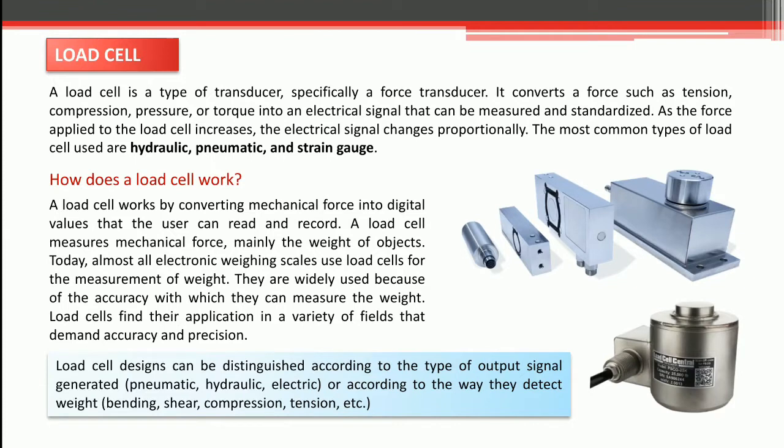Now what is a load cell? Load cells are elastic devices that can be used for measurement of force through indirect methods, through the use of a secondary transducer. This load cell utilizes an elastic member as the primary transducer and a strain gauge as the secondary transducer. When the combination of the strain gauge and elastic member is used for weighing, it is known as a load cell.